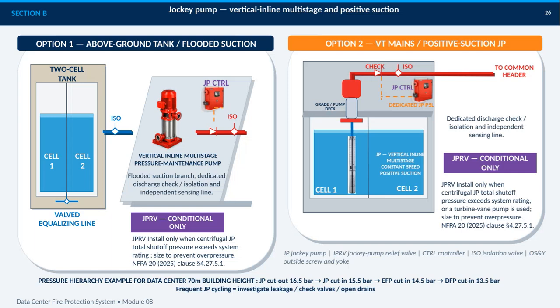This slide presents two installation options for a jockey pump, using a vertical inline, multi-stage, constant speed pump with positive suction. The key requirement is a reliable, flooded, or otherwise positive suction arrangement, with a dedicated discharge check valve, isolation valve, and independent sensing line. Option 1 uses an above-ground 2-cell tank. The cells are connected by a valved equalizing line, and the jockey pump control system monitors pressure through its dedicated sensing line. Option 2 uses the water tank mains or another positive suction source, with the pump located at the grade or pump deck and discharging to the common header.